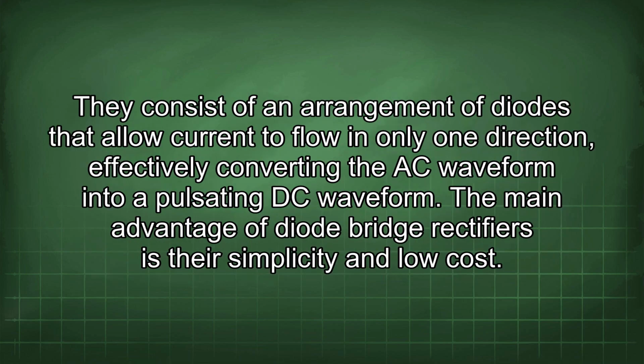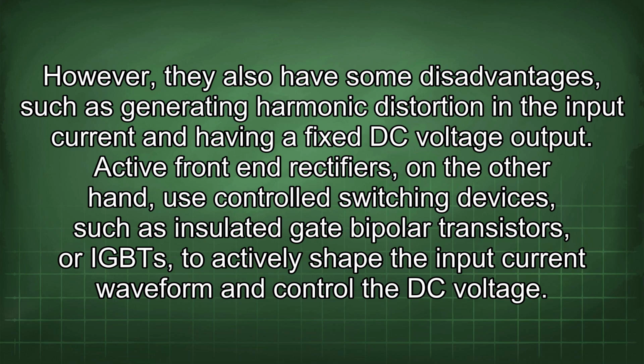They consist of an arrangement of diodes that allow current to flow in only one direction, effectively converting the AC waveform into a pulsating DC waveform. The main advantage of diode bridge rectifiers is their simplicity and low cost. However, they also have some disadvantages, such as generating harmonic distortion in the input current and having a fixed DC voltage output.